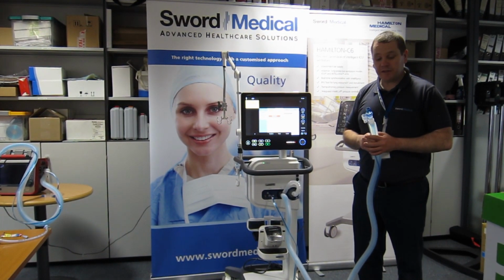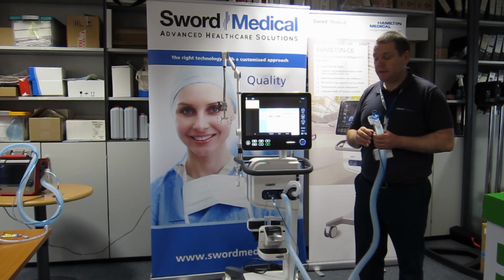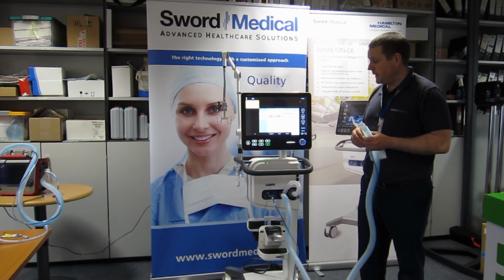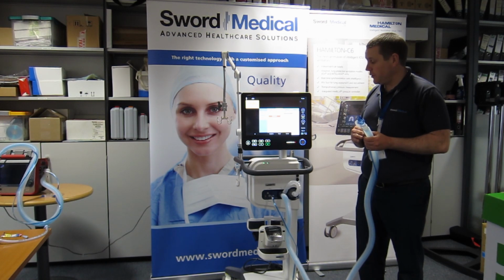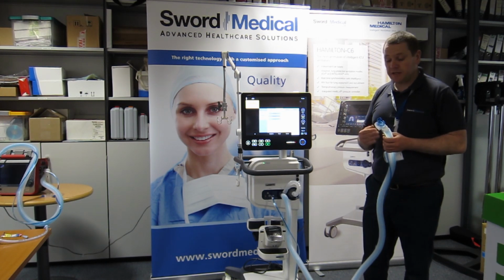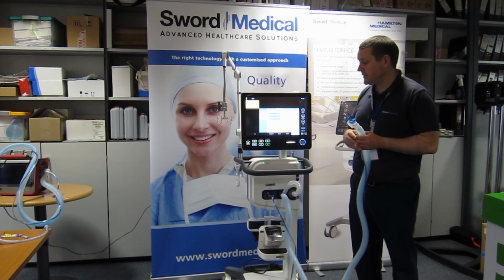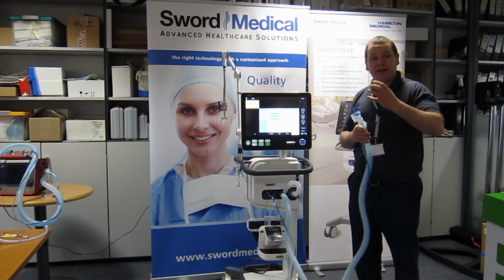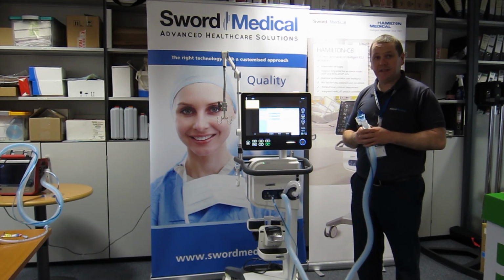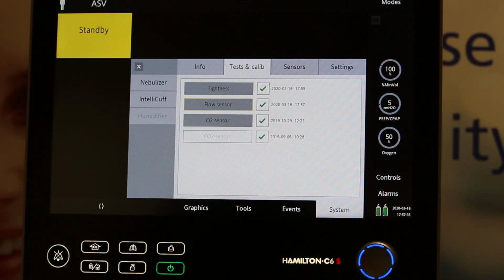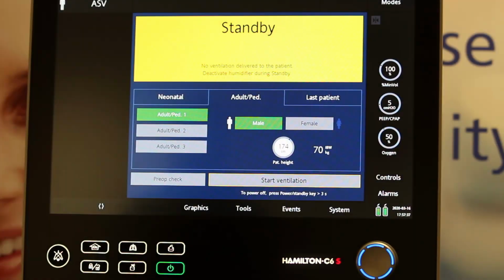So if it does fail the flow sensor calibration, we'd say do it again, paying attention to the prompts. And if it fails a third time or a fourth time, you may need a new flow sensor, but we've never come across them failing out of the packet. Normally what catches people is that they haven't done the manoeuvre within the 15 seconds allocated. So that circuit is now ready to use. Very important.